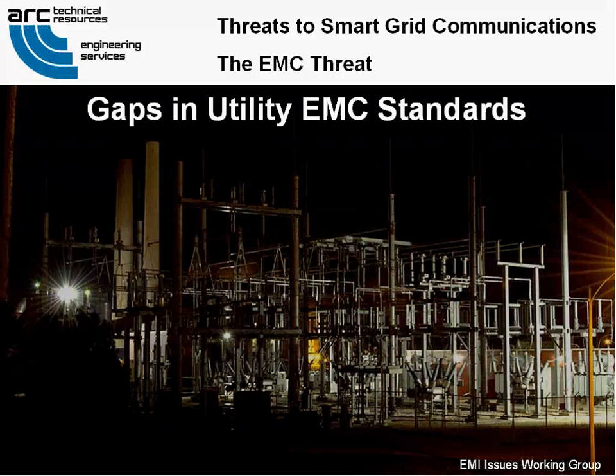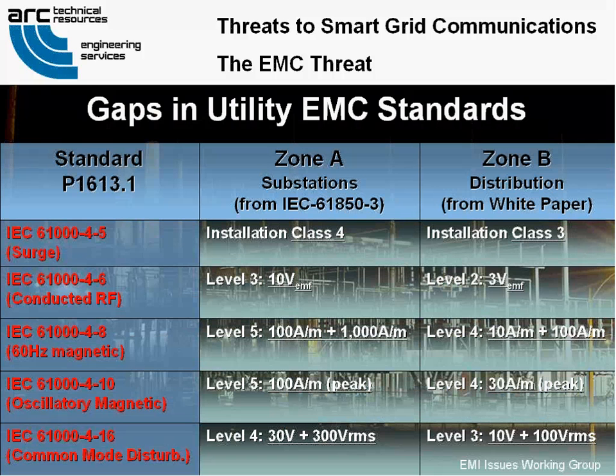Gaps in American utility EMC standards. These five immunity tests were referenced in the P1613.1 draft. IEC 61850-3 invoked the test levels for substation products that were used in the draft and called out for products used in Zone A, that's inside the substation fence, as shown in the middle column. Zone B is defined in the draft as outside the substation fence in the distribution network and requires a lower test level in each case.